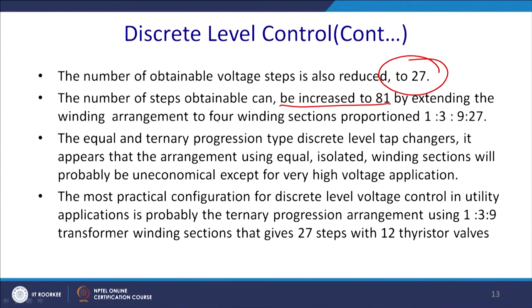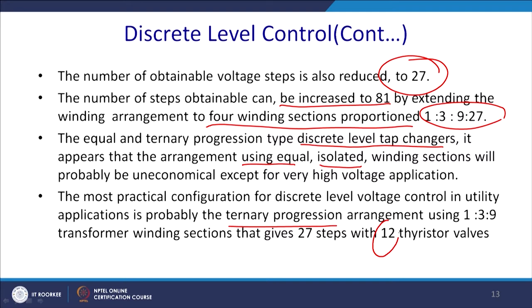By extending the winding arrangement for the 4 winding section proportional to 1, 3, 9, 27. The equal and the ternary progression type discrete level tap changers: it appears that the arrangement using equal isolated winding sections would probably be uneconomical, except for very high voltage applications. So, previously this kind of splitting has been preferred. The most practical configuration for discrete level voltage control in utility application is probably the ternary progression arrangement using 1, 3, 9 transformer winding sections, which gives you 27 steps with 12 thyristor valves. That is one of the biggest advantages of the discrete level control.